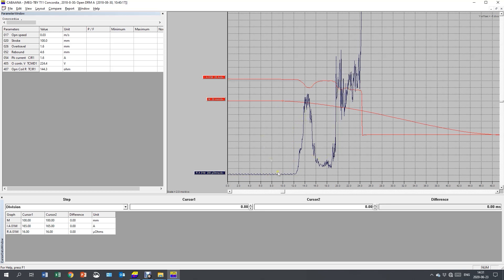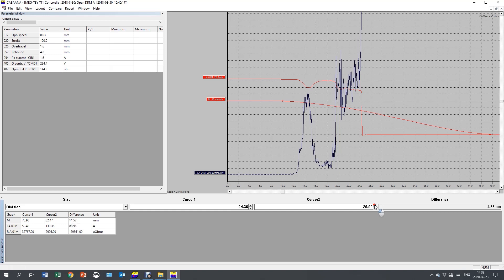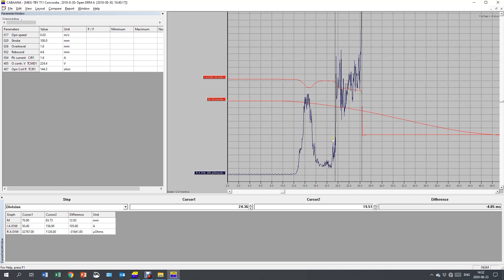Now I need to put the cursor in the right position. I put the first cursor where the breaker opens. And that is where the current drops at around 24 milliseconds. I need to move it exactly to the dropping point there. And I go to the second cursor and I put it to the big resistance step. So I move it to this slope. And now I can read out the difference in millimeters from the two cursors.